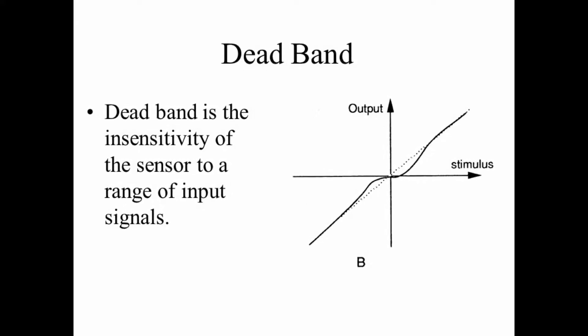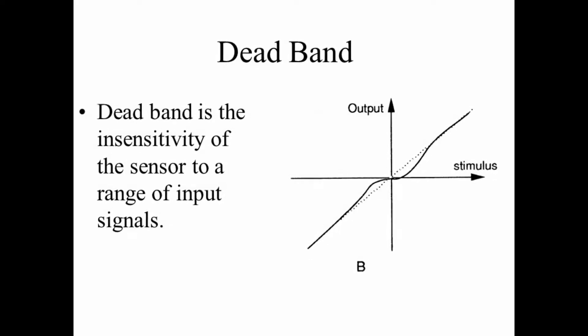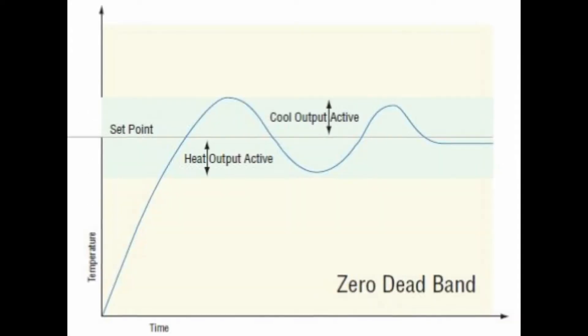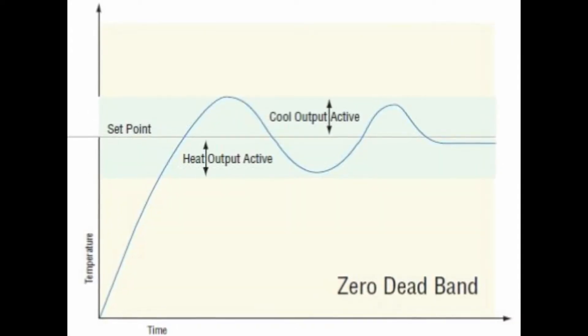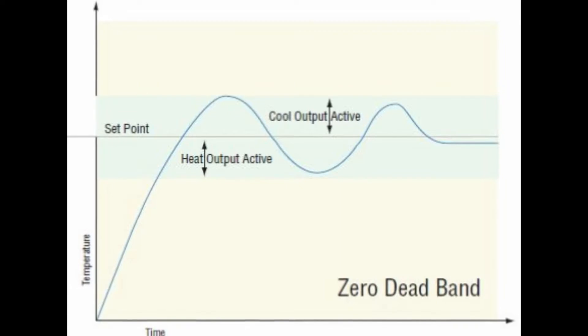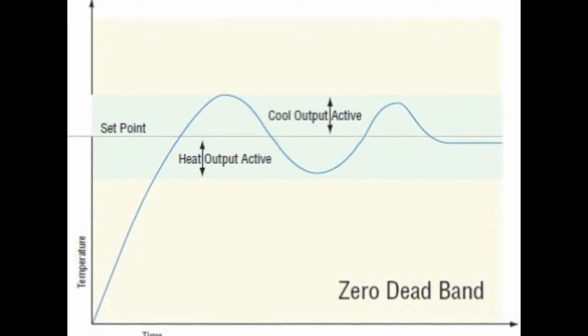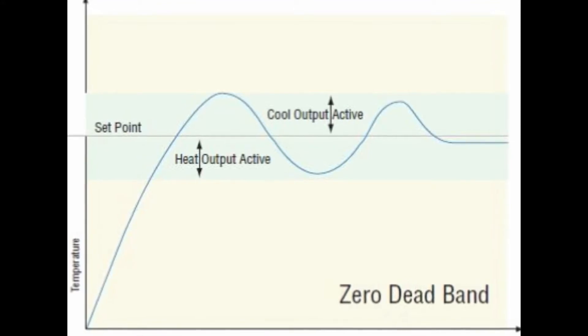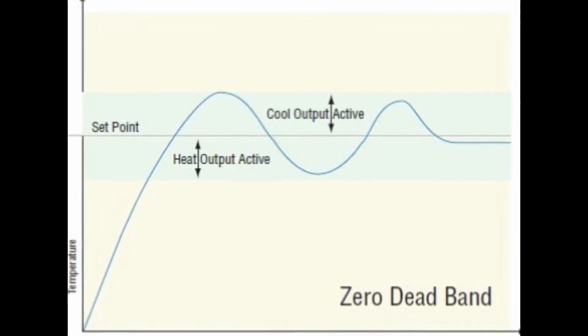The threshold of positive and negative pressure around zero where no change in output is detected is called the dead band. The dead band is responsible for the dog leg-shaped characteristic noticed in the measurement output when the pressure changes from positive to negative and vice versa, as it passes through the null point of the diaphragm.